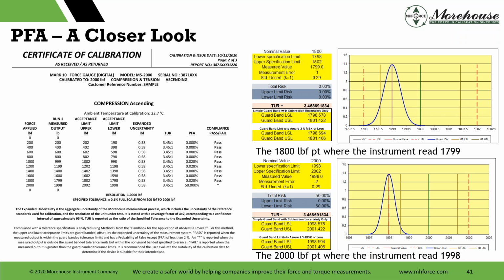Start looking at this in more detail. You have nominal value points. Here we're looking at 2 points in this example. We're looking at 1800 and we're looking at 2000. And here at 1800, up here, we're looking at lower specification 1798, upper 1802. And when we calculate the risk, it says, hey, with 2% risk or less, as long as my measurement falls between 1798.594 and 1801.406, we're good. And if I come up here, my measured value is 1799.0. That falls between the lines. If you look at it up here, everything is within the tolerance limit. On the 2,000 pound point, I look at it, come down here.